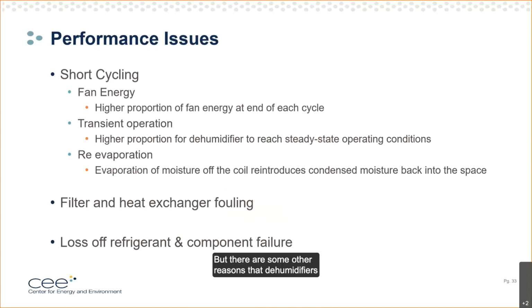But there are some other reasons that dehumidifiers don't perform as well as they should. The main one is short cycling. So like other HVAC systems, short cycling can impair performance. Recall the cycle I showed earlier. There's always some fan energy at the end of a cycle. So for shorter cycles, there's proportionally higher fan energy.